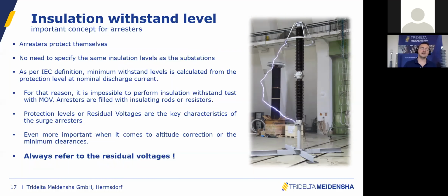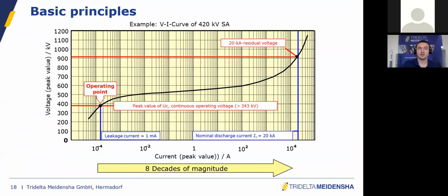It's also very important when it comes to altitude correction and minimum clearances. You always have shorter clearances with surge arresters. So you have the possibility to reduce the distance between two phases, or also from phase to ground. So just to summarize, always refer to the residual voltage.